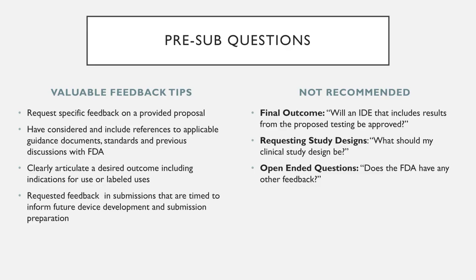And whenever requesting study designs, the FDA is always going to take the position that you, the medical device company, know much more about your device and the current literature and your competitors than what the FDA knows. So, for instance, a question like, what should my clinical study design be? Very often, the FDA is just going to kick that back and say, hey, you have to propose something and we can give feedback on that. We can't recommend something for you. We just don't have the expertise.